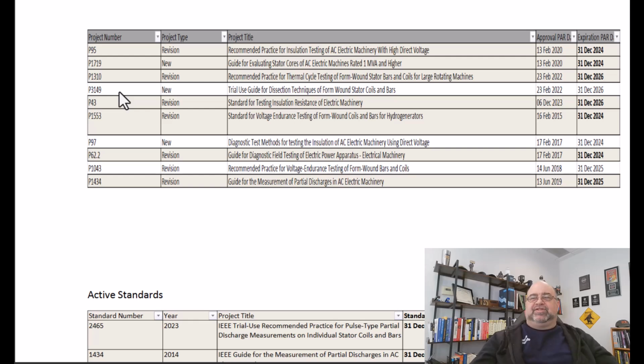So that was very important, because then the OEM happened to be there because it was a concern, and we said, "Okay, here's some ways to fix this." Well, we've got a bunch of those in the field, and they aren't failing. Okay, well, great. If they do fail in the same way, and they come in and they get rewound, add this.